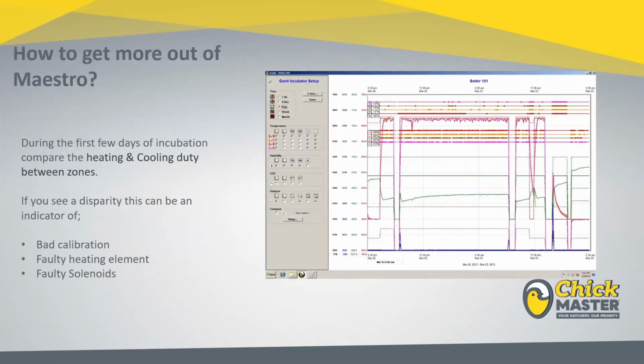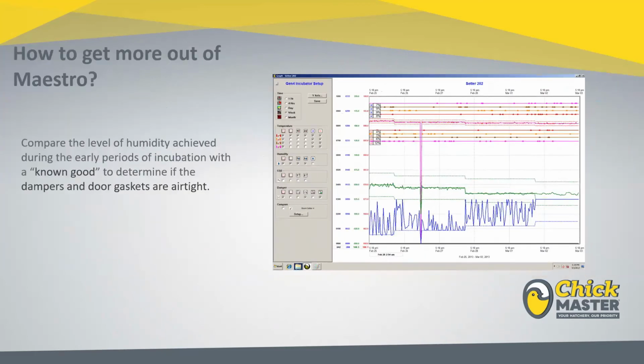So when we take it a step farther, once we get past warm-up, something that's a great idea to do is look at consistency from zone to zone when we look at the amount of heating or cooling duty between the zones. So oftentimes you see here where it's highlighted in the top portion of this graph where that bottom or zone 4 had extended period of heating. I think in this case that's the red line, so that's actually zone 1 that had an extended amount. And oftentimes this can come from a bad calibration or a faulty heating element, or again could be faulty solenoids where you have a chilled water solenoid that is leaking. So it's important to monitor machines once they've come up to temp, and once all the egg mass is at operating temperature, the machine should settle down and all the zones should be fairly consistent.